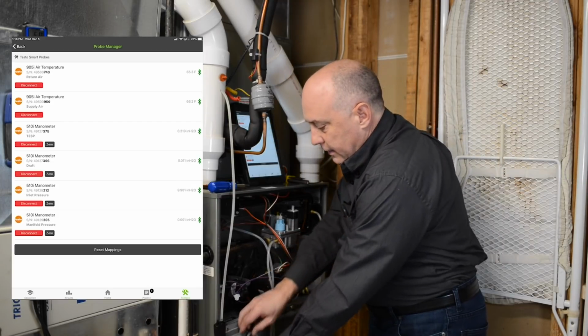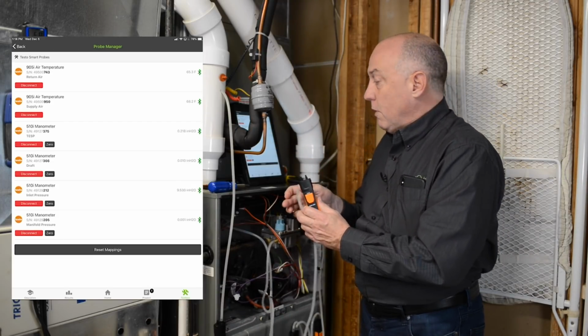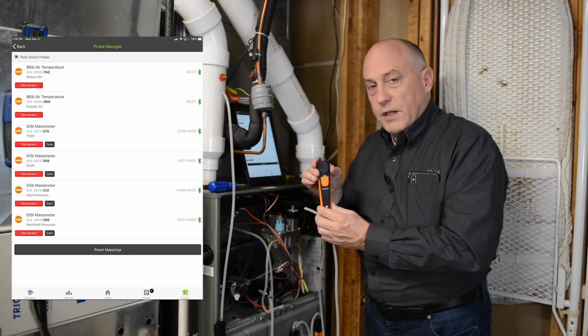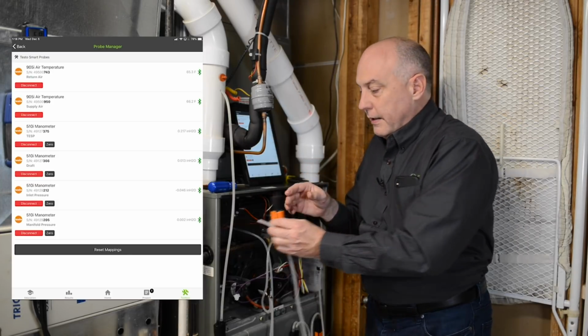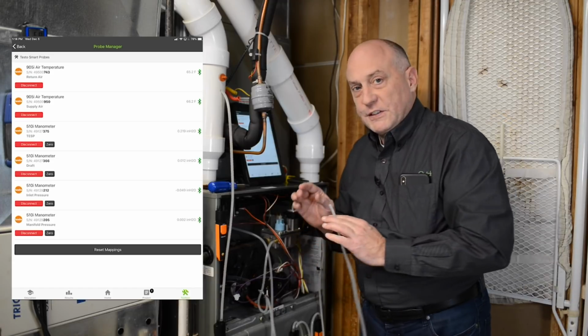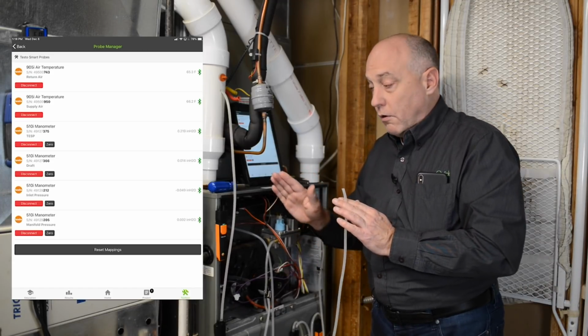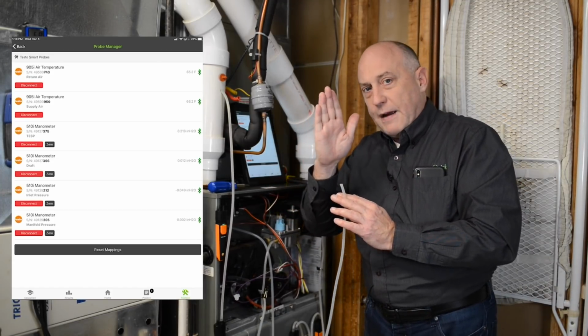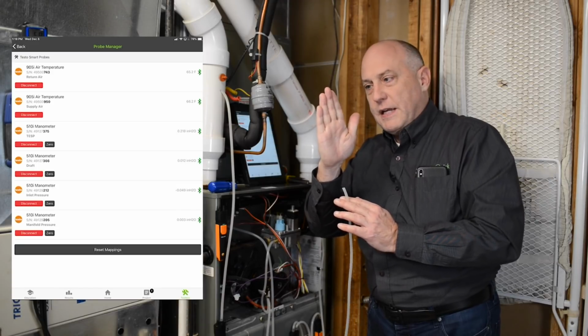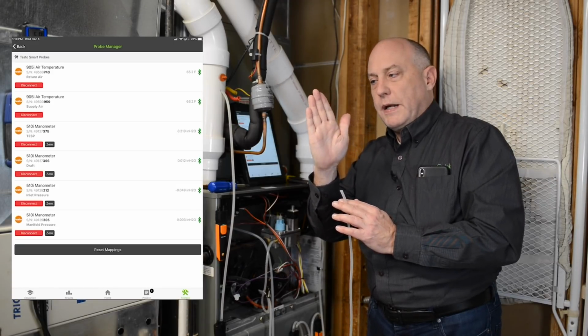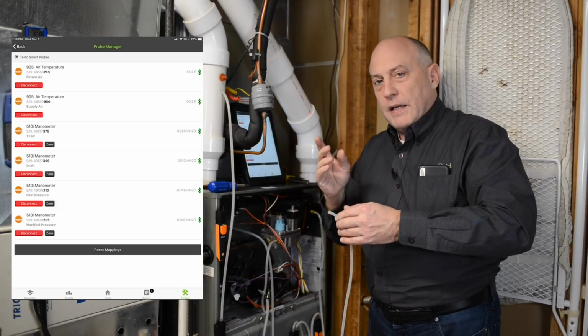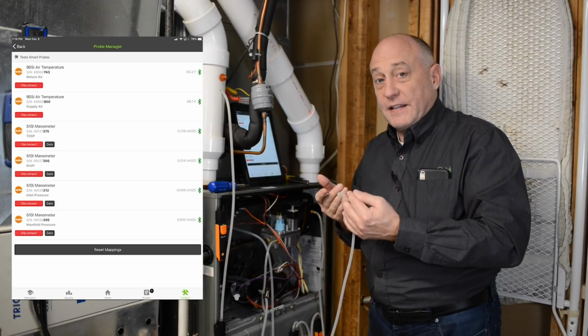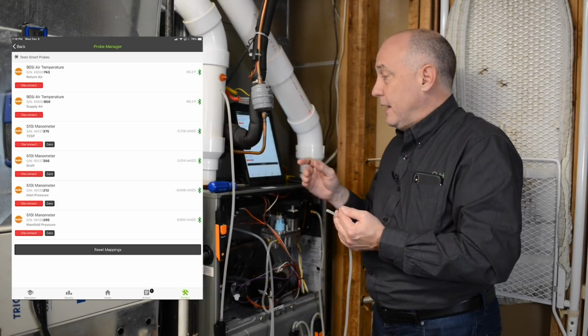So I'm just going to take that, pull the tube off this thing. You want to make sure when you're zeroing out these Testo manometers that you leave them flat on the surface that you're going to adhere them to, or on a flat surface, because the diaphragm itself is so sensitive that if you take that manometer and calibrate it this way and lay it on its back, it's going to affect the calibration. You can actually play with that and see that on your manometer.